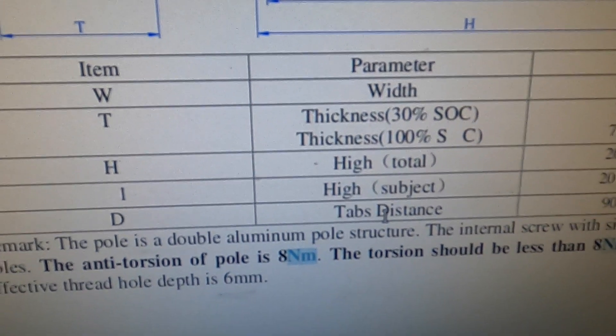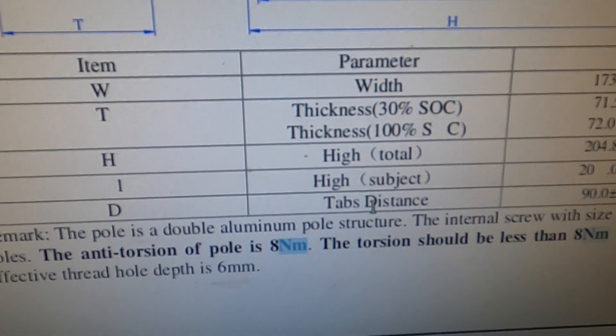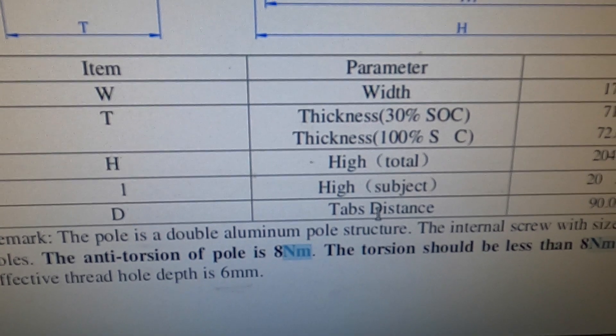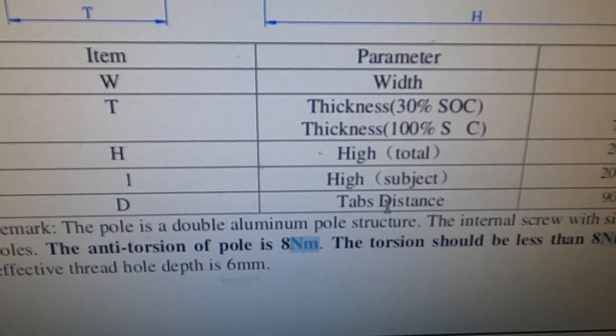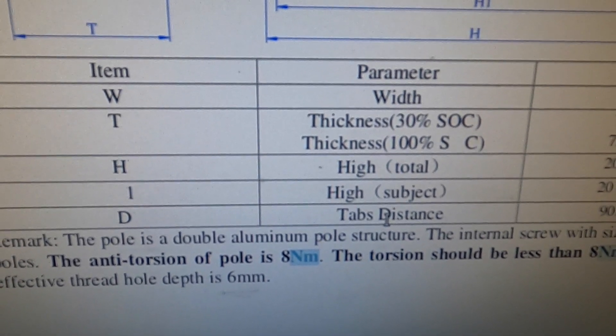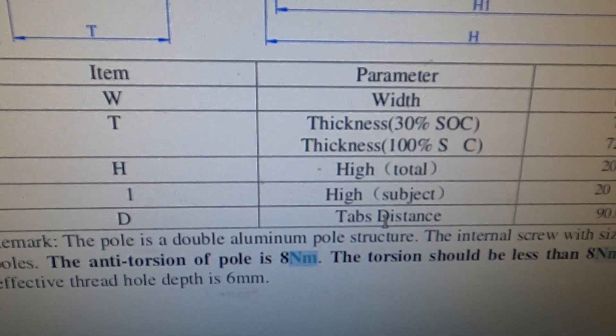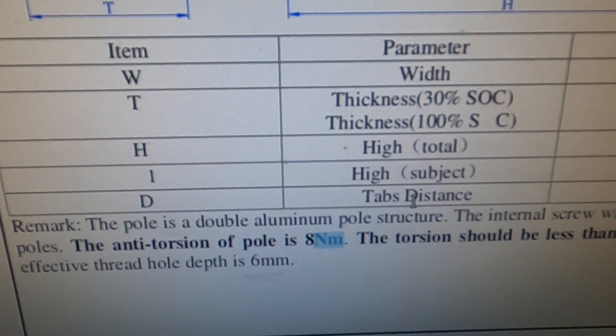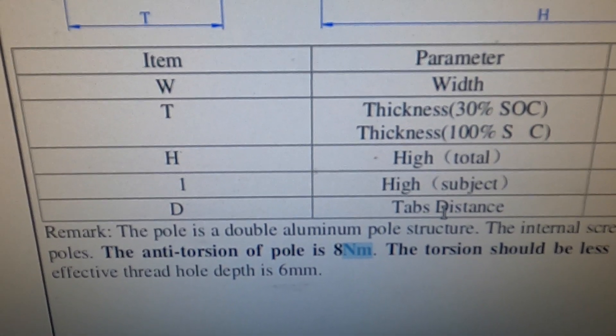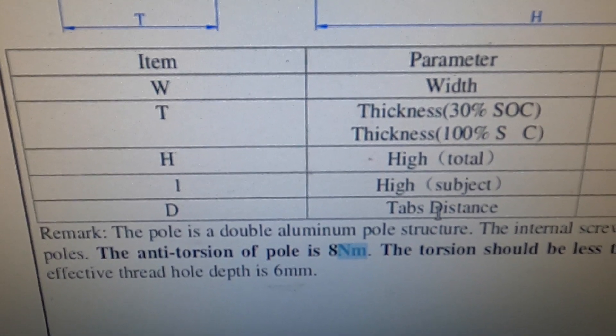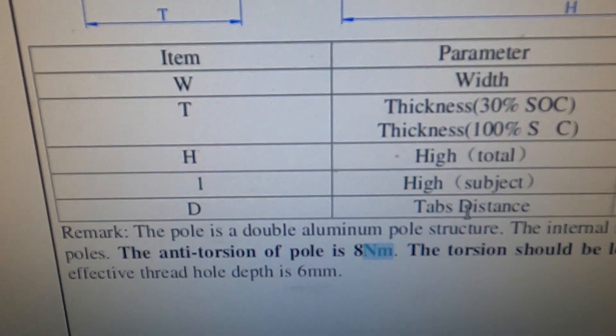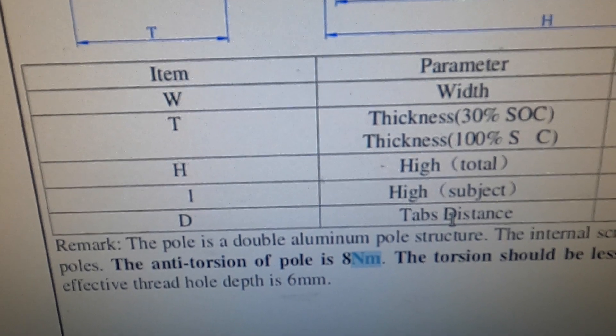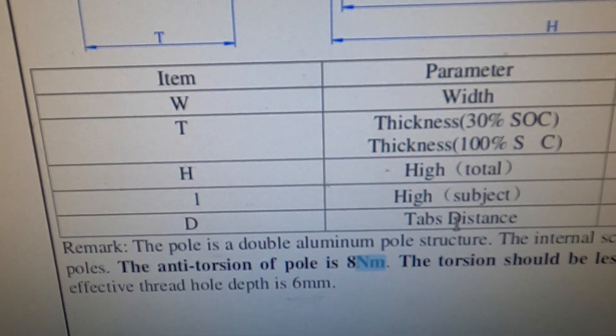So the important part of that is anti-torsion of pole is 8 NM and employing my best English I interpreted that to mean that the torque specification for the screw in the hole on the top of the terminal was 8 Newton meters.